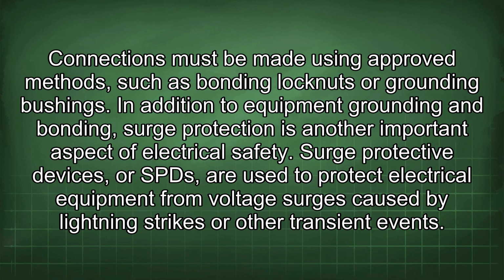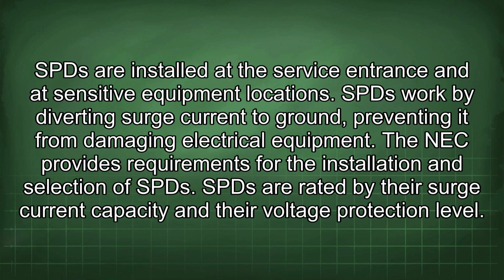In addition to equipment grounding and bonding, surge protection is another important aspect of electrical safety. Surge protective devices, or SPDs, are used to protect electrical equipment from voltage surges caused by lightning strikes or other transient events. SPDs are installed at the service entrance and at sensitive equipment locations. SPDs work by diverting surge current to ground, preventing it from damaging electrical equipment.